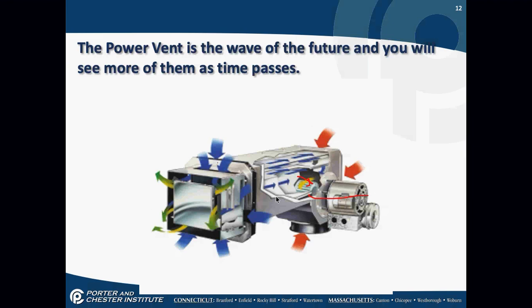Okay. Sequence of operation of an oil furnace with a power venter. Thermostat calls for heat. Power venter starts. Power venter proves draft by the pressure switch closing. That energizes the primary control, which energizes the burner. The power venter runs the entire time the call for heat is going on. Entire time the call for heat is happening. The power venter continues to run. Thermostat satisfies, signals the power venter to shut off. Power venter does basically a post purge cycle. Power venter continues to run after the burner shuts off to get all the products of combustion out of the house. Once that post purge cycle is done, the power venter shuts down.